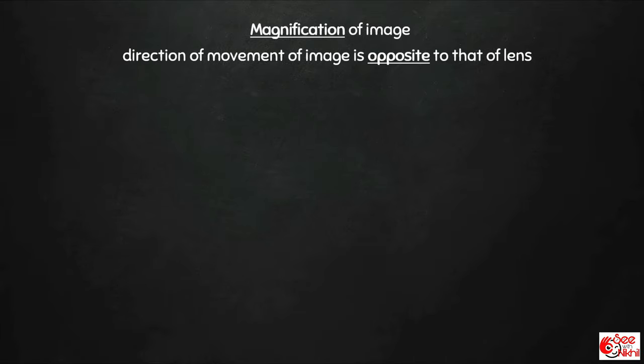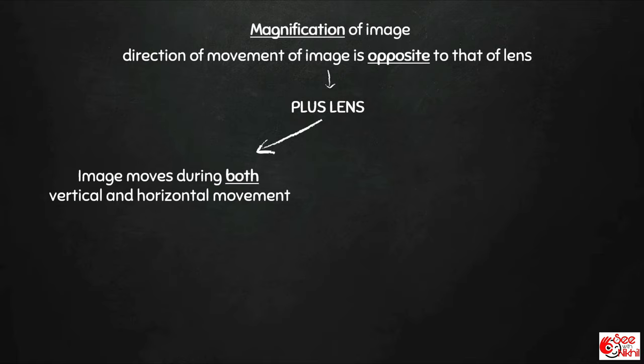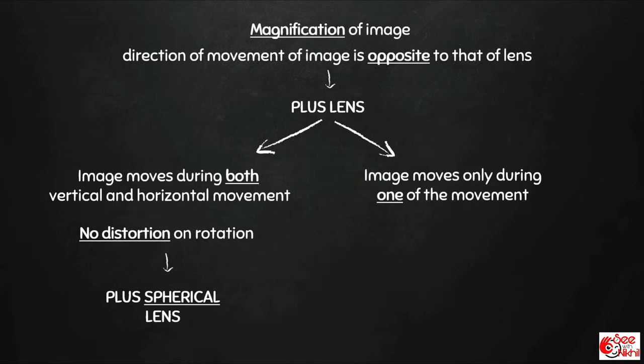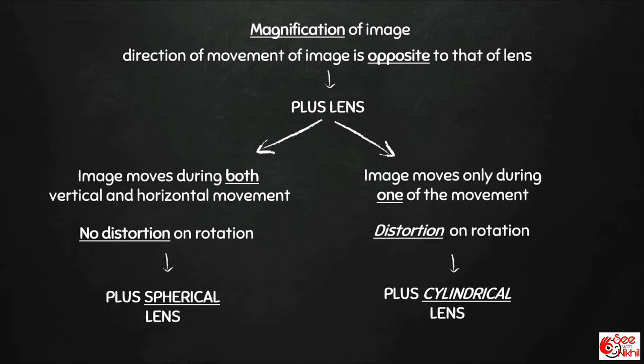If there is magnification of image and the direction of movement of the image is opposite to that of the lens, that means it's a plus lens. If the image moves during both vertical and horizontal movements and there is no distortion on rotation, that means it's a plus spherical lens. But if the image moves only during one of the movements and there is distortion on rotation, that means it's a plus cylindrical lens.